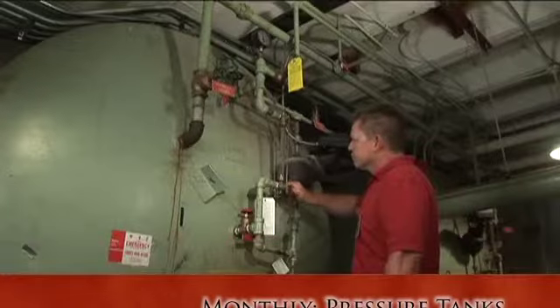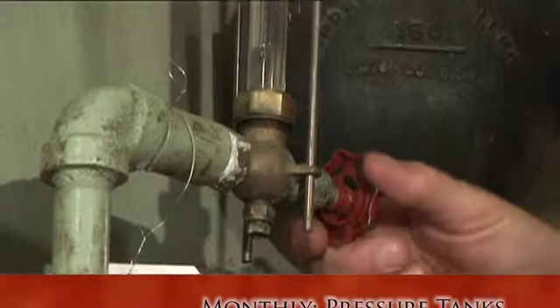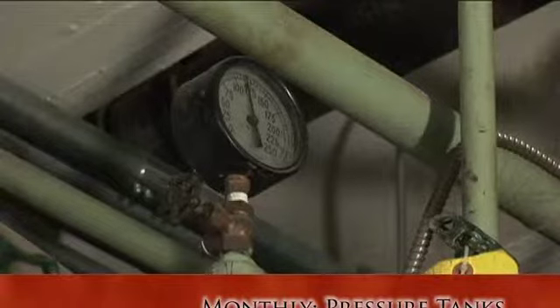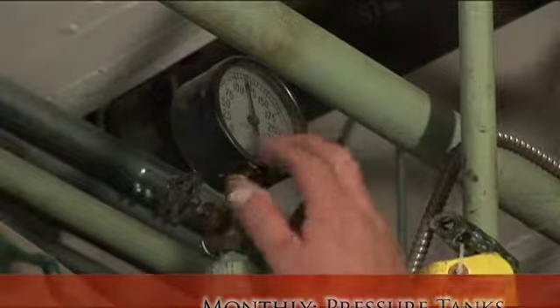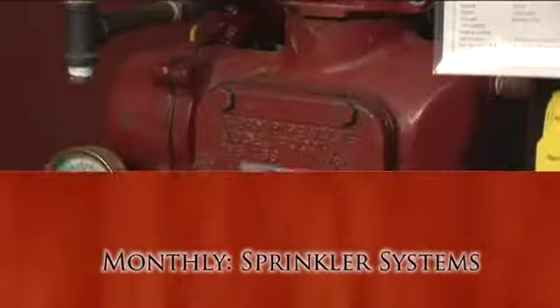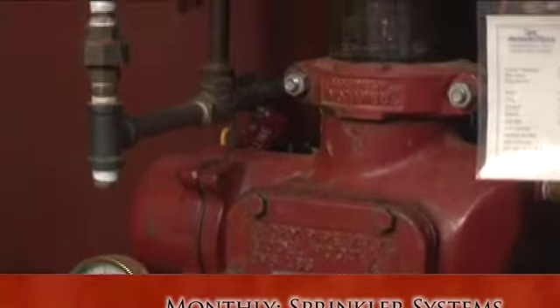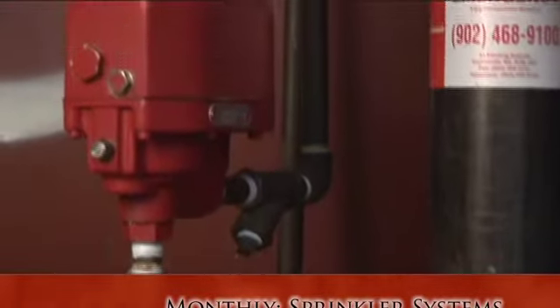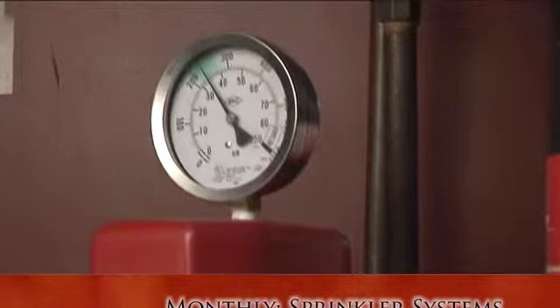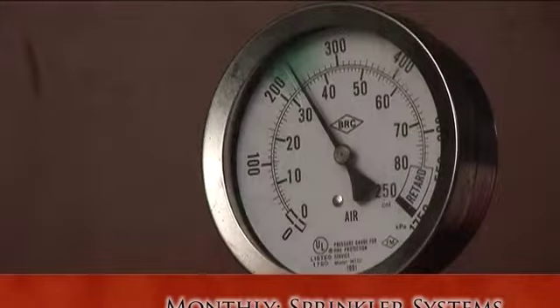Pressure tanks must be inspected at least once a month to ensure the water level and the tank pressure are correct and at the recommended manufacturer levels. Dry pipe sprinklers have a pressure gauge that must be inspected to ensure that the pressure is within the specified range. The proper range number should also be posted on or near the pressure gauges for easy reference.